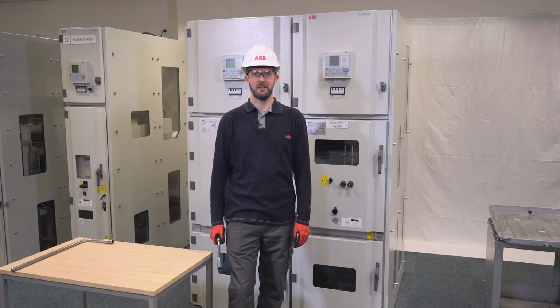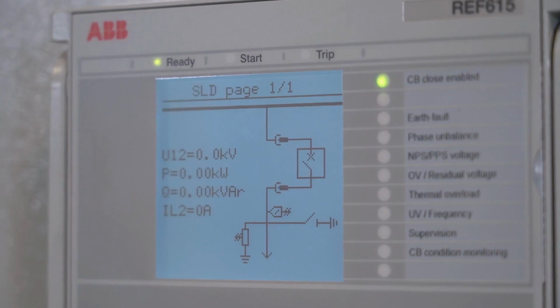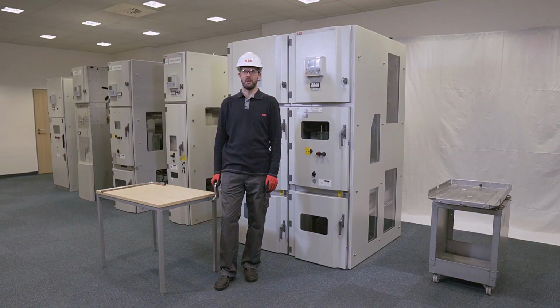Rack the breaker in standard pace until you see positive indication that the breaker is fully in service position and you feel a hard stop in the rotational movement.